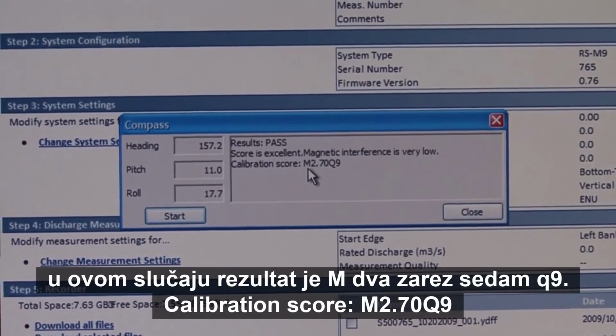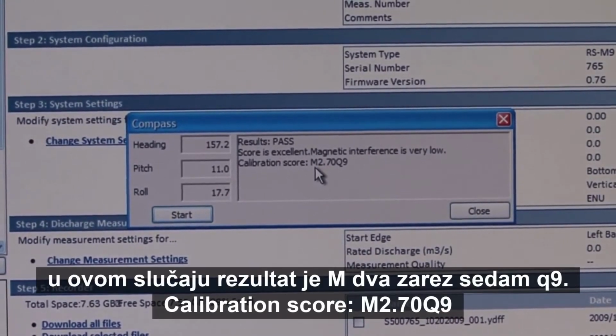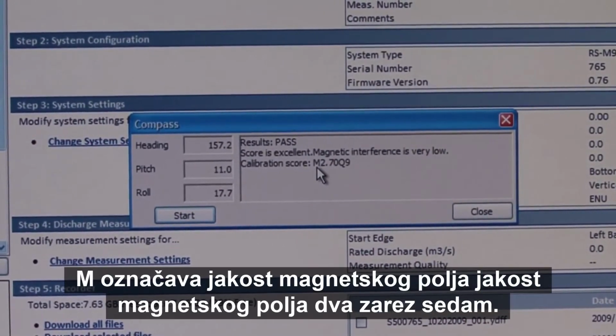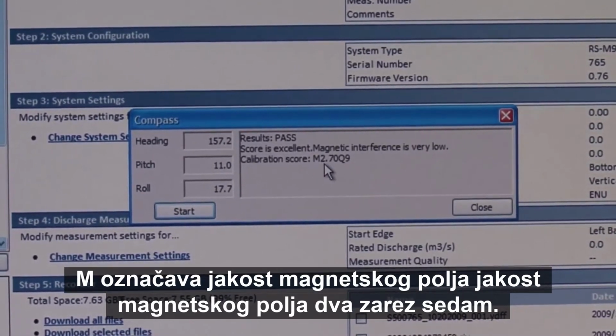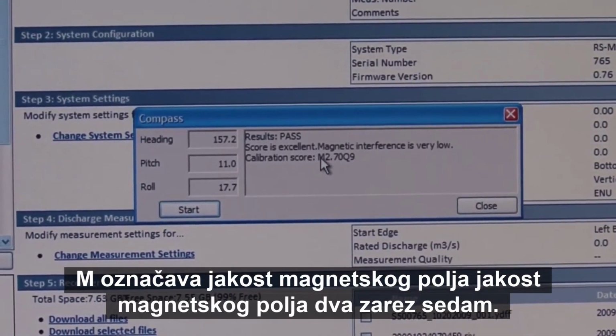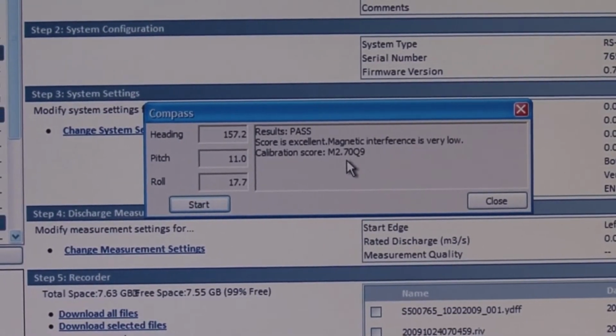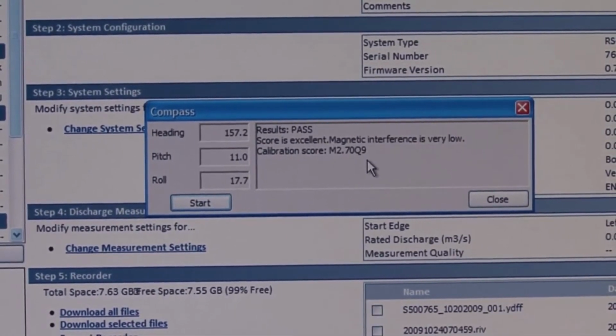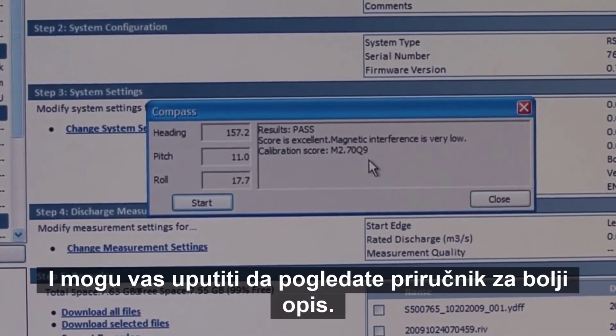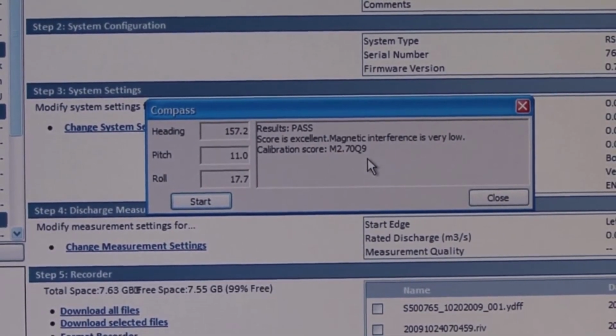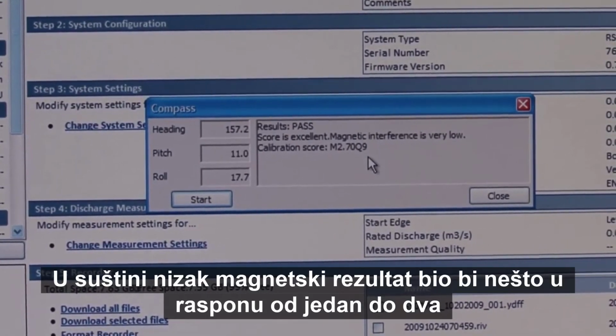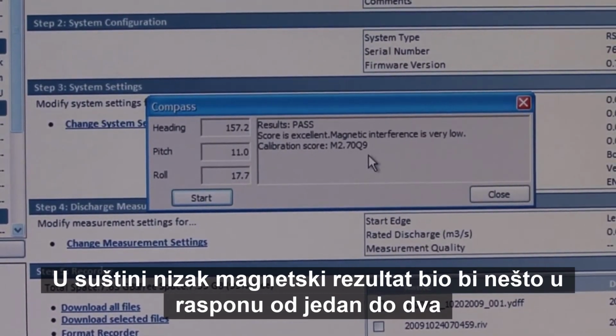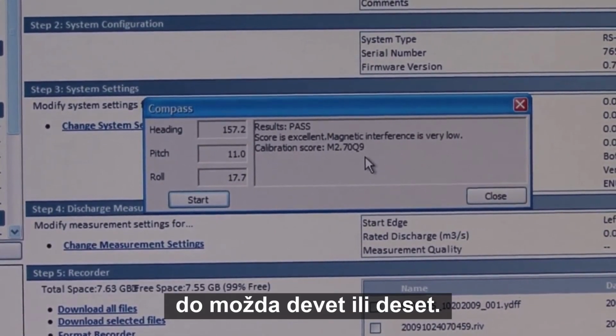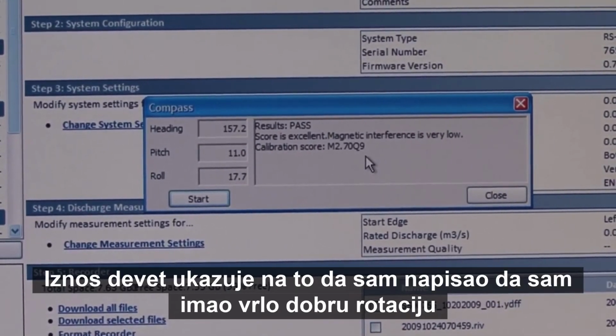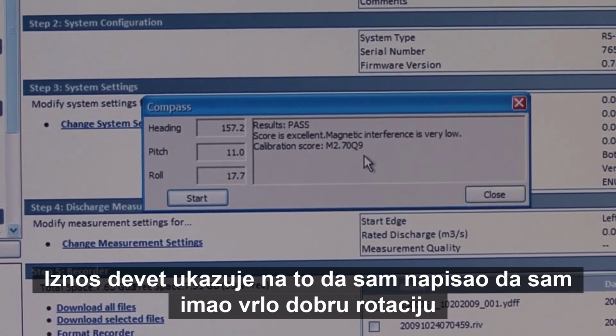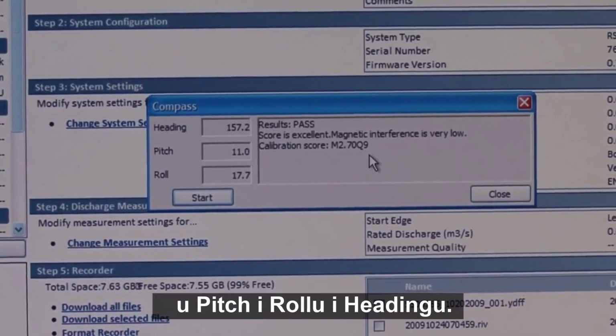In this case, the score is M2.7Q9. The M stands for the magnetic field strength of 2.7. The quality is 9, and I can let you refer to the manual for a better description. Essentially a low magnetic score would be something in the range from 1 to 2 up to maybe 9 or 10. And a quality of 9 indicates that I had a very good rotation on pitch and roll and heading.